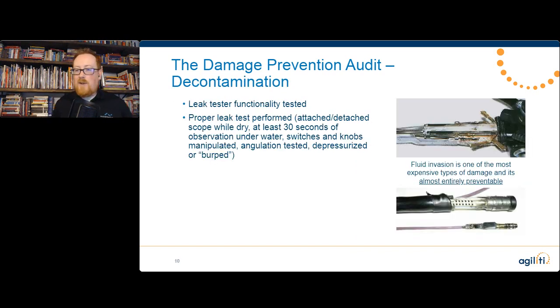Leak testing, we've talked about it multiple times already. It has to be done every single scope. Fluid invasion is extremely detrimental to these. One thing I definitely want to recommend, though, is that in addition to doing your regular leak testing, you need to test your tester. What are you doing to ensure that your leak tester is actually pushing through the correct amount of air to ensure that it's actually doing what it's supposed to be doing?